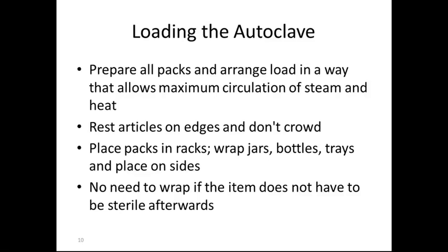Loading the autoclave. Prepare all packs and arrange the load in a way that allows maximum circulation of steam and heat. So you want to make sure that there is space in between each package. Rest articles on the edges, but do not crowd them. Place packs in racks, wrap jars, bottles, and trays, and place them on the sides. No need to wrap if the item does not have to be sterile afterwards.